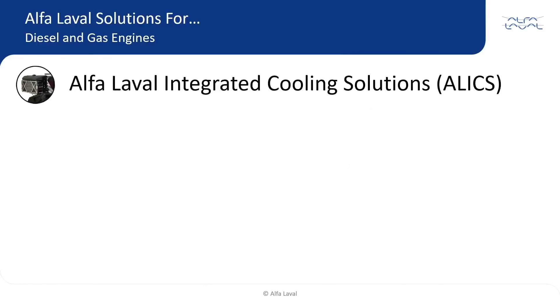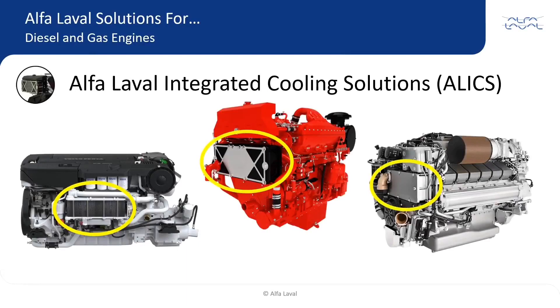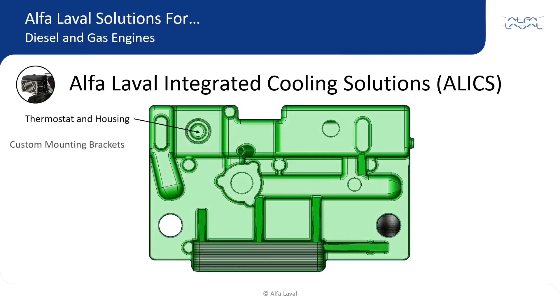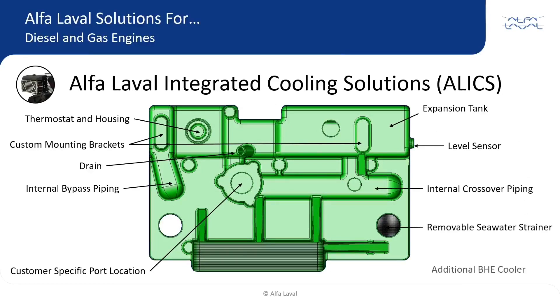Alfa Laval Integrated Cooling Solutions, or ALICS for short, are unique custom solutions designed to bolt directly to a customer's engine. ALICS is an integral solution for many engine manufacturers dating back to the 1990s. Gasketed titanium plates are typically used to be able to cool with seawater, then eventually disassembled, cleaned, and returned to 100% efficiency. Custom ALICS solutions allow the customer to incorporate many features often distributed throughout the engine into one compact package. The complete ALICS is assembled and fully tested prior to shipment, so the customer simply bolts it in place and connects to the ports.